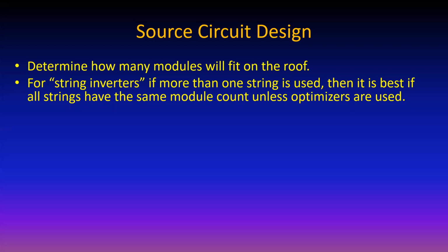optimizers are used. But if you use optimizers, that restricts the inverters you use. The inverter has to be one that talks to the optimizers, because there's a lot of communication going on in the process of optimizing the performance of the system. The optimizer, though, is also good in this system because they are perfect for serving the function of rapid shutdown. And again, that's a fire requirement for the most part, a safety requirement. The optimizers are located underneath the modules, but they are DC to DC, and they shut down if the DC flow is interrupted to the inverter.